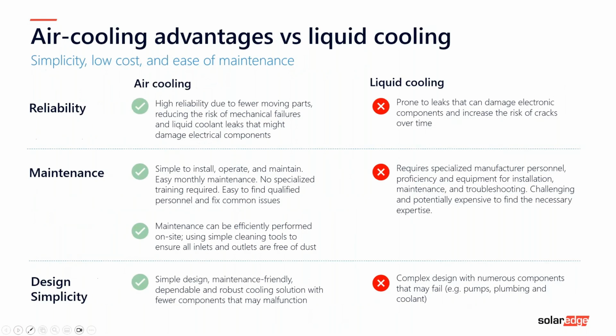So people ask, what's the difference between air cooling and liquid cooling? Well, anybody with a car radiator knows that can have leaks, it does corrode, it does require some maintenance, and the fans can get blocked. So we opted for air cooling. The maintenance is incredibly easy, very easy monthly maintenance, just check that the fans are clean, things like that. Very simple to design, very simple to work, and very reliable.